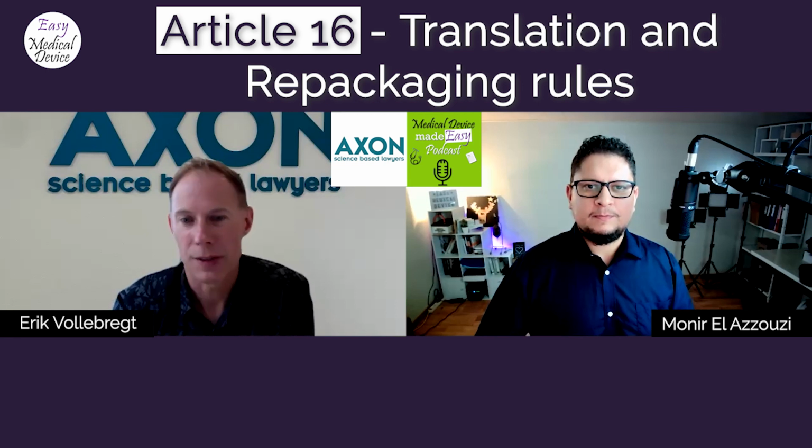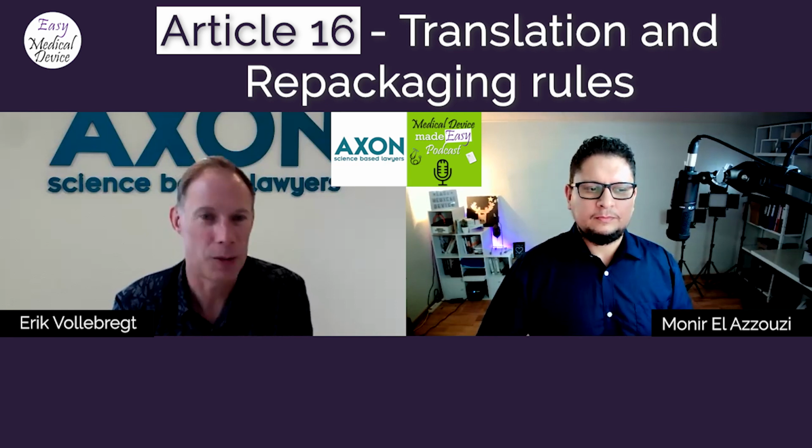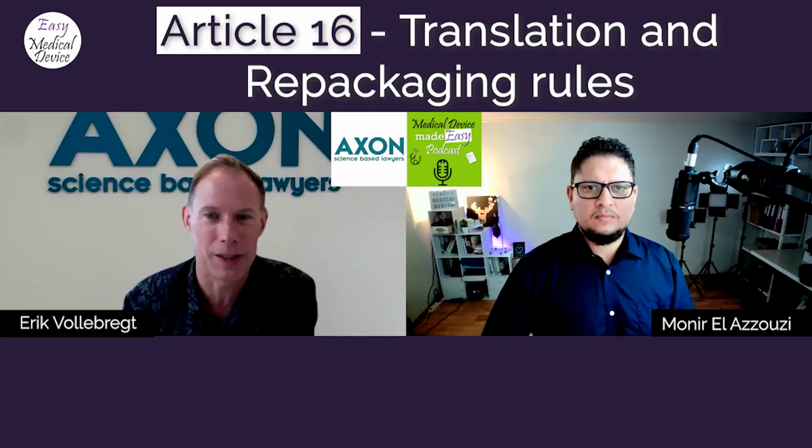Mm-hmm. Well, that's of course a bit of a consequence of the system, that if you require that you go to a notified body that has been notified for that scope, and you have a very exotic product for which not many notified bodies have a scope, and then also you only want this certification of your quality system and nothing else, then it is really difficult as a distributor or an importer that is independent to go to a notified body now and say, hey, will you certify this? Yeah, for a lot of notified bodies, this is actually not a very interesting activity.